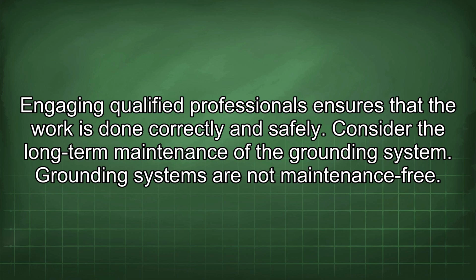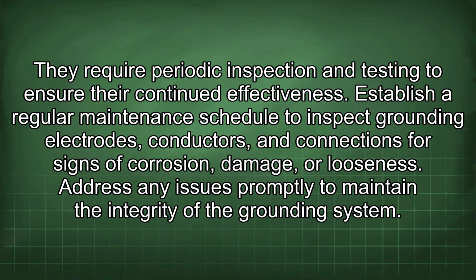Consider the long-term maintenance of the grounding system. Grounding systems are not maintenance-free. They require periodic inspection and testing to ensure their continued effectiveness. Establish a regular maintenance schedule to inspect grounding electrodes, conductors, and connections for signs of corrosion, damage, or looseness. Address any issues promptly to maintain the integrity of the grounding system.